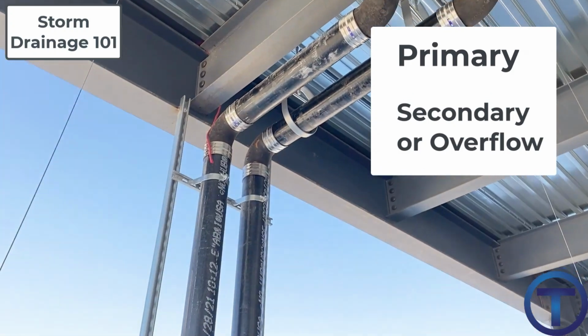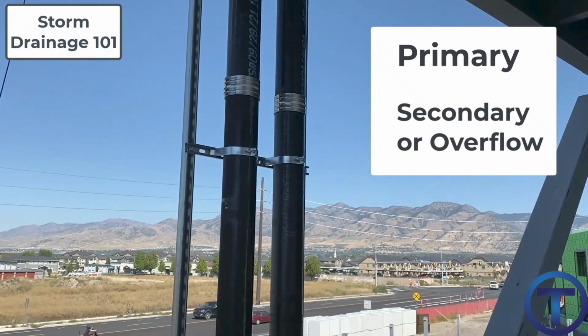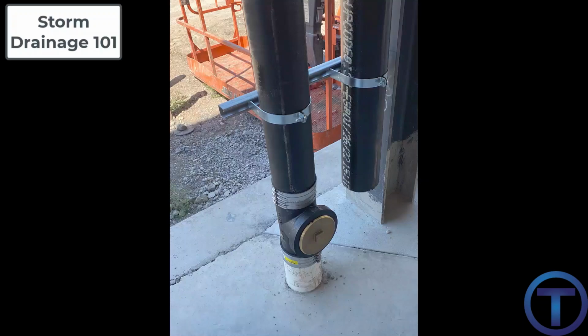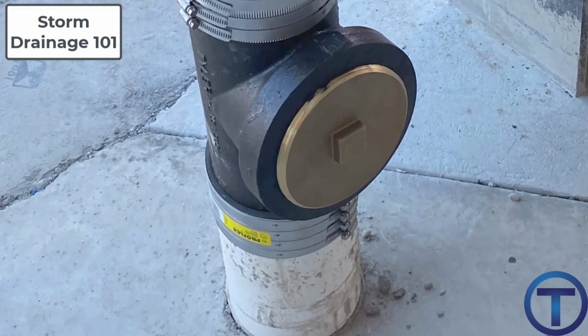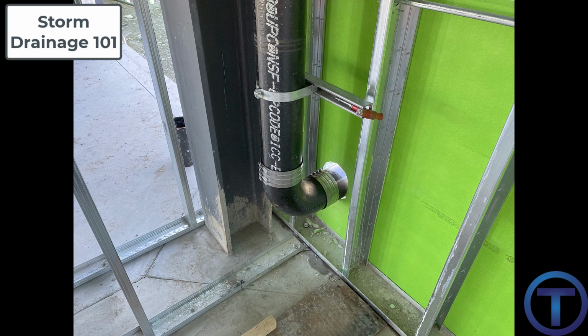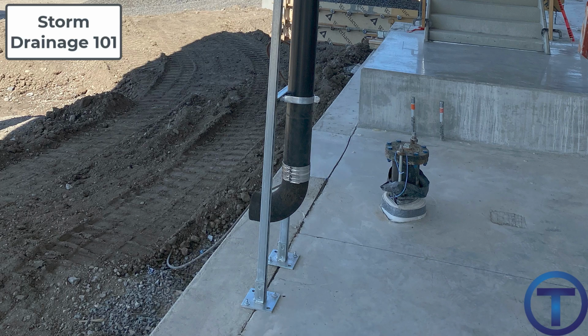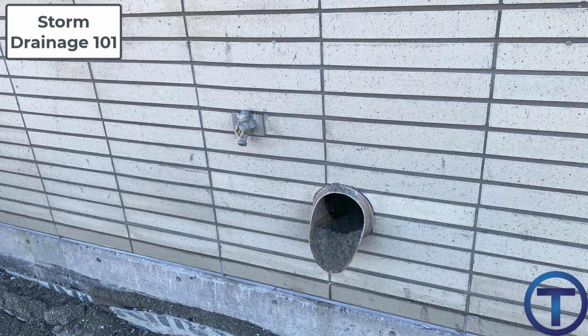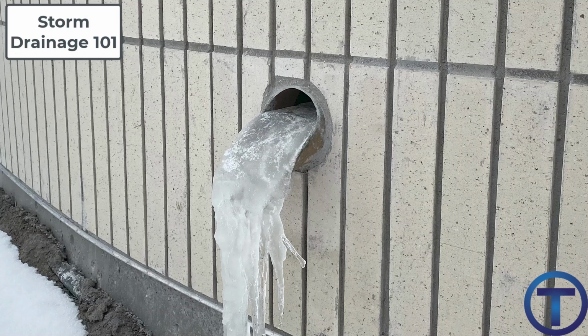Now, the primary drain typically runs down and connects to storm drainage outside the building. That may be a pipe that runs underground to some other storm drain system. The secondary drain is required to convey the water to an outside location where it can be observed. Typically, this is a scupper coming out the side of the building. We have an example here of a cow tongue type scupper, a large brass fitting that's just going to dump that water out away from the building. This is so that if, again, the primary gets plugged, the secondary can convey the water out, but you would want to know that's happening. And so, when you see water coming out of there, then it's time to do some maintenance.